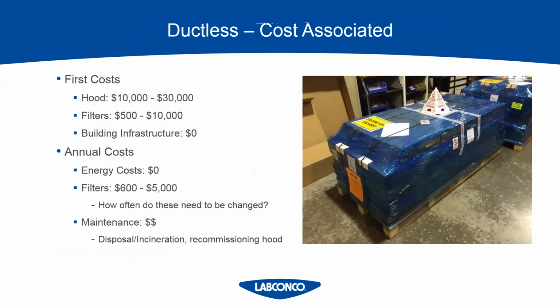The costs associated with a ductless hood include the first costs, which have a very large range because the DH3 can do much more than a DH1. So the range, for purposes of comparing with a fume hood, starts at $10,000 and goes up to about $30,000 for the hood alone. Then we have the filters, which could range from $500 to $10,000 per hood.